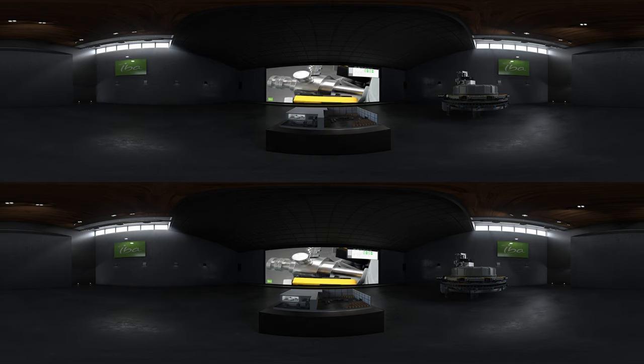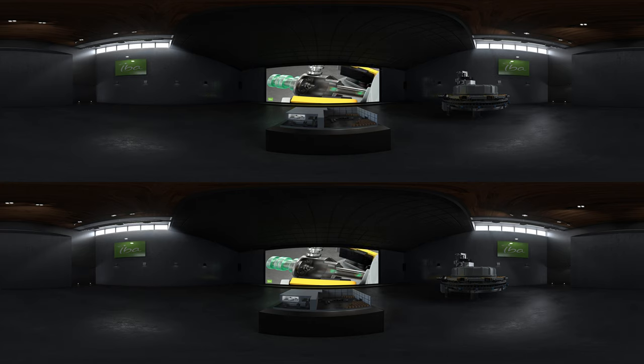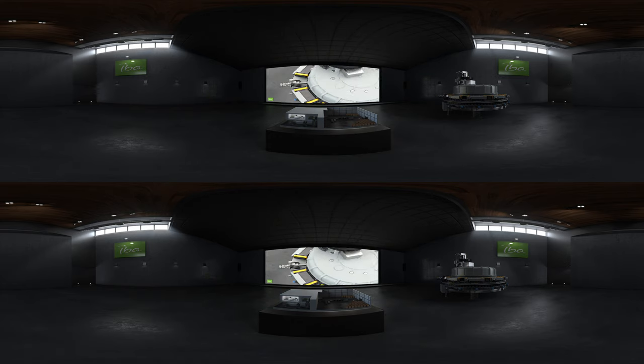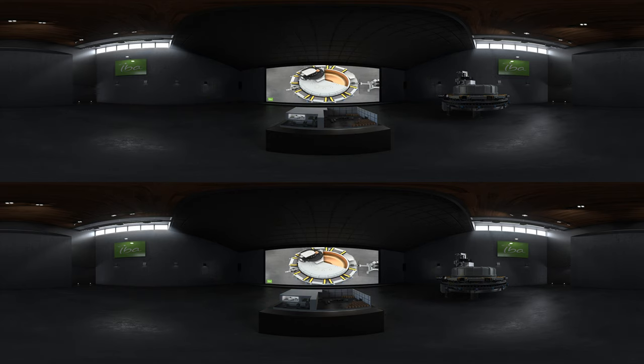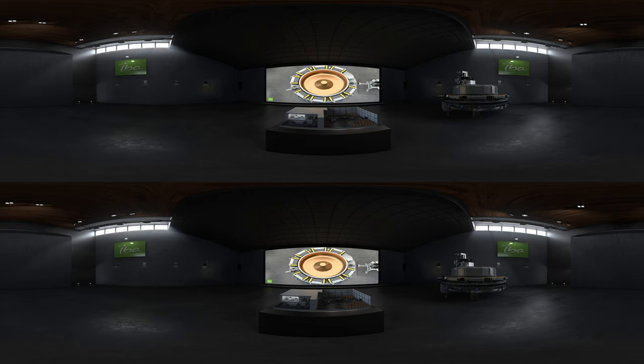The cathode, located on the left side of the Rhodotron, generates the electrons that are accelerated in the cavity. When electrons reach the inside of the cavity, the RF system produces an electric field between the external wall of the cavity and the central pillar. The electrons are therefore attracted by the pillar. When going through it, the polarity of the electric field is reversed in such a way that when travelling in the second part of the cavity, the electrons are accelerated a second time.